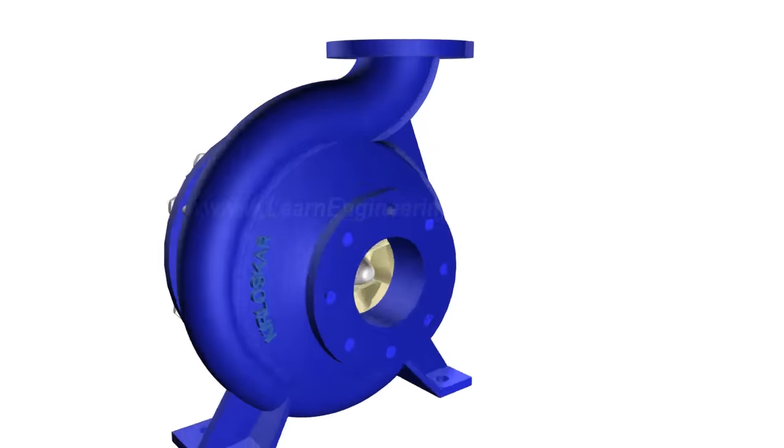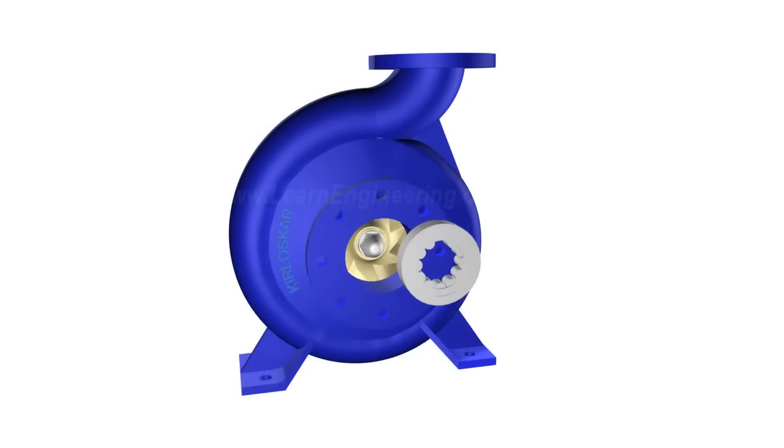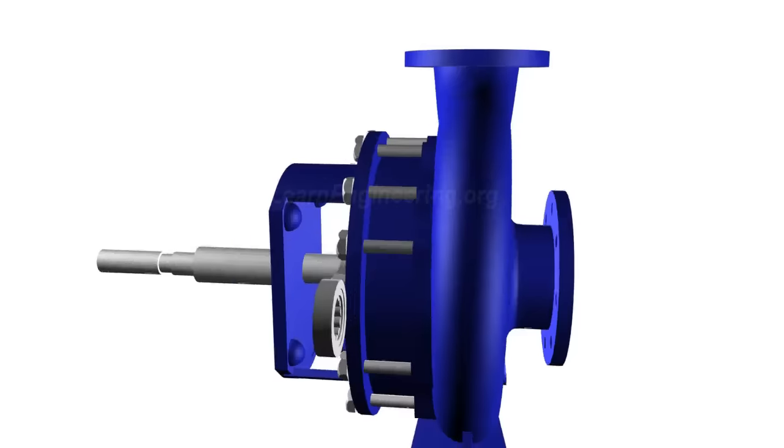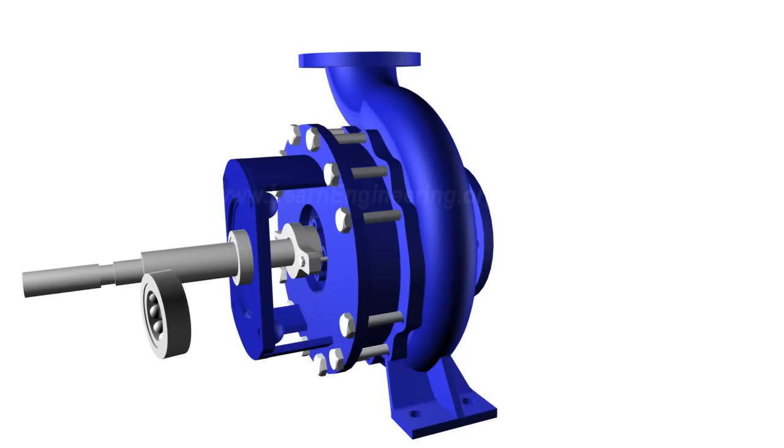The impeller is mounted on bearings. But at the suction side of the impeller, it is not advisable to fit a bearing since it will block the flow. So bearings have to be fitted at the other end. This means the impeller is mounted like a cantilever.